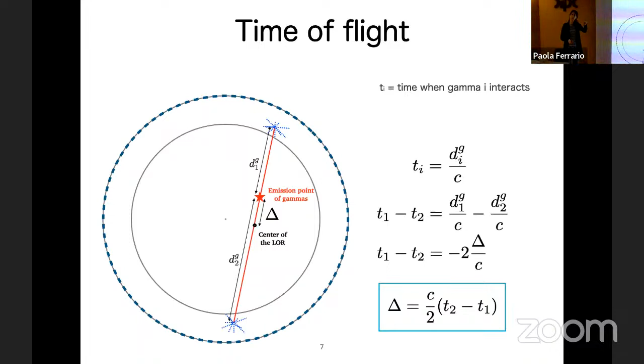Here you can see in the case of a conventional PET without time of flight, you draw a line and then you assign the same probability to any pixel on the line. So any point on the line has the same probability of having emitted the gammas. But if you have this information of the time difference, you can constrain a point on the line. Of course, this is not a point because you have a finite resolution in your time measurements. So this resolution gives you the width of this Gaussian distribution. So you basically can constrain a segment on the line.